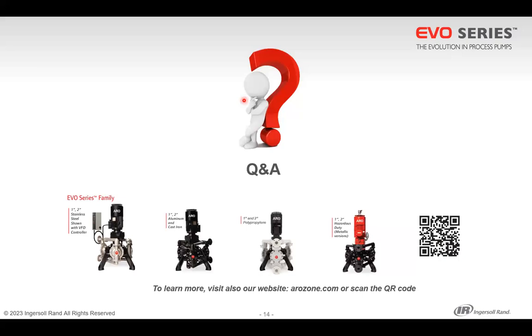With EVO, we had tried, not with this customer. We had some trials with other powders like fumed silica, but what is important is that what can be pumped by an AOD powder pump can also be pumped by an EVO. It's just a matter of doing the right fluidization.